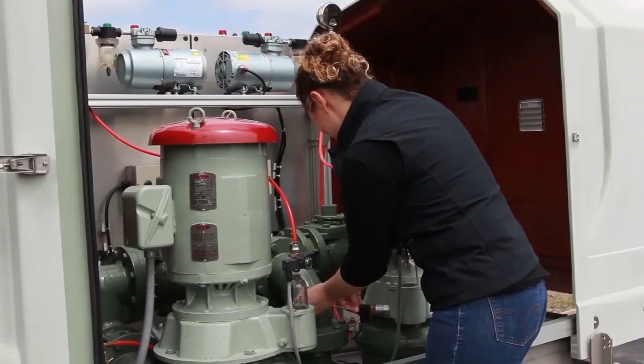Let's begin by using our screwdriver to remove the Sonic Start DIN connector cable assembly from our Sonic Start probe. Simply remove the Sonic Start DIN connector cable assembly from the Sonic Start probe. Next, you will use your adjustable wrench to remove the Sonic Start probe from the motor adapter.